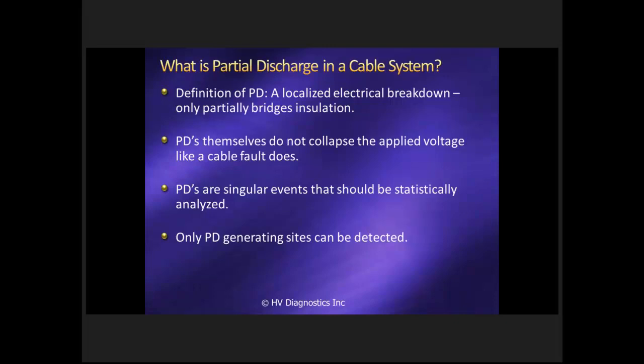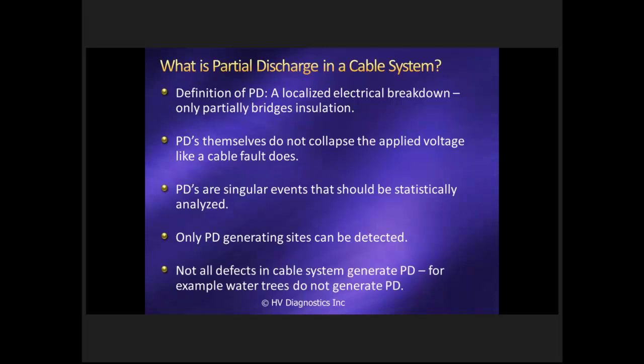And this may be obvious, but to a lot of people it's not that obvious. Only partial discharge generating sites in the cable can be detected. If, for example, you have a water tree, and you could have several 100,000 water trees in the cable, they don't generate PD. So you won't be able to find water trees using PD. If you have a void in the cable, or a defective termination, for example, where they're cutting too deep into the insulation, you could find it with PD. Obviously not all defects in a cable generate PD, for example, the water trees I mentioned.